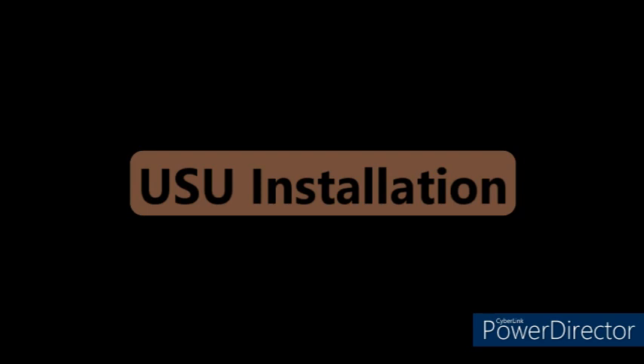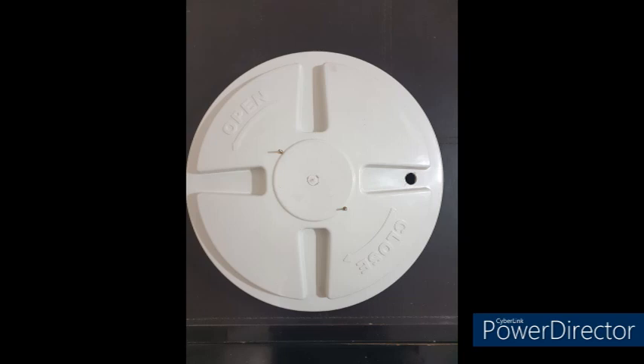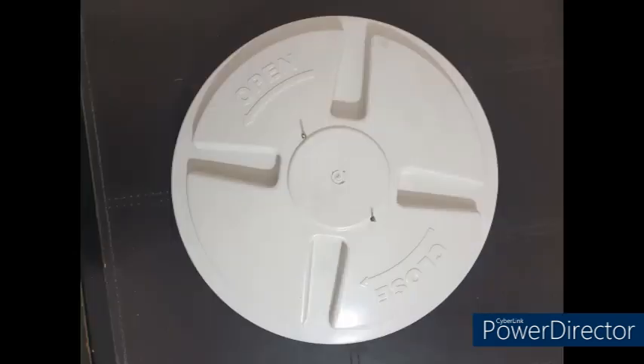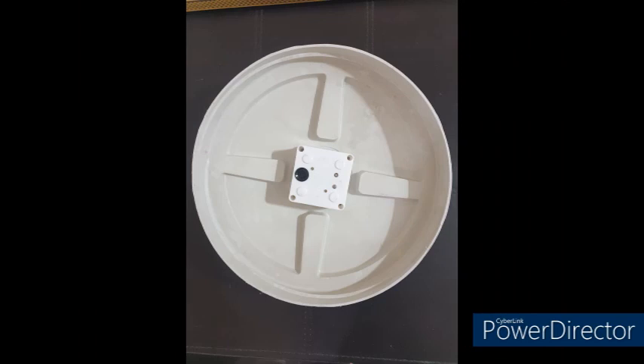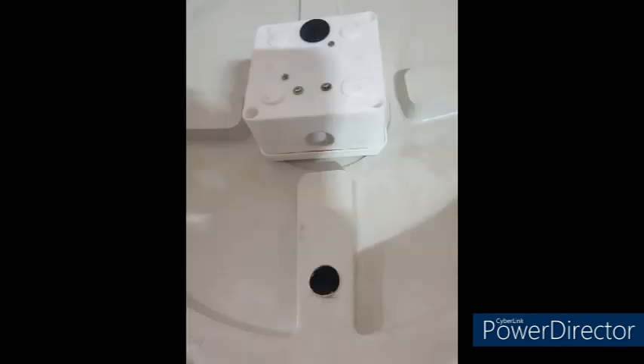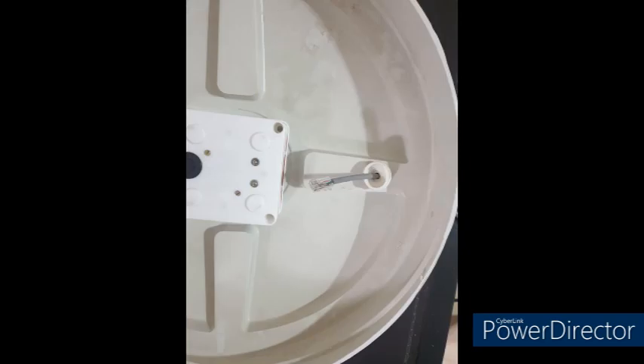Installation of USU and its cable. 3 holes have to be cut through the lid: 2 for mounting and 1 to pass the cable. Mounting holes are 3 mm and the cable pass hole is 25 mm in diameter. The USU has to be mounted at the center and on the bottom side of the lid, with sensor facing downward and in perfect horizontal condition. The Cat6 cable has got 2 rubber grommets.